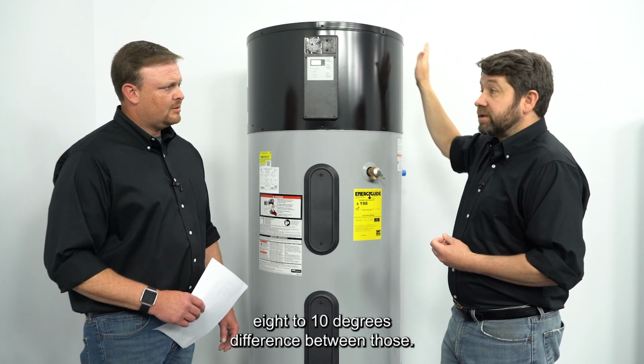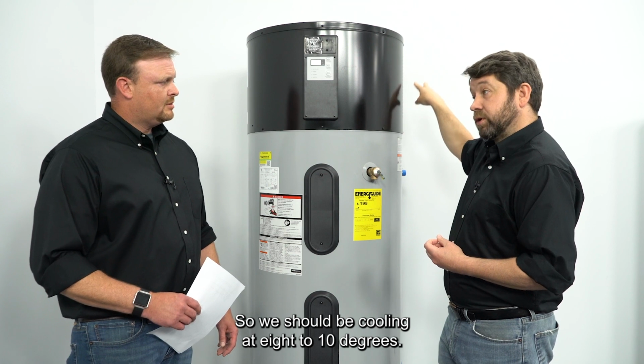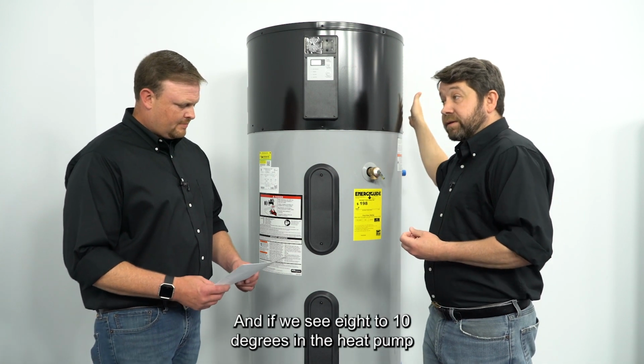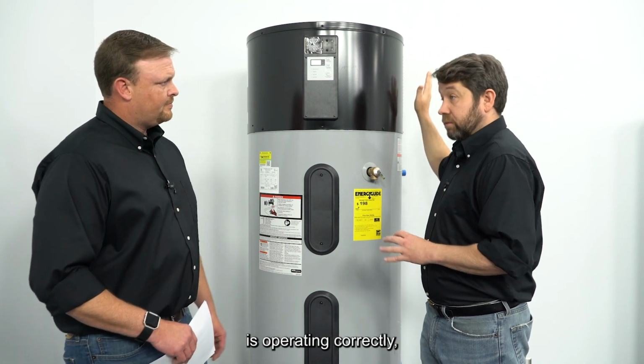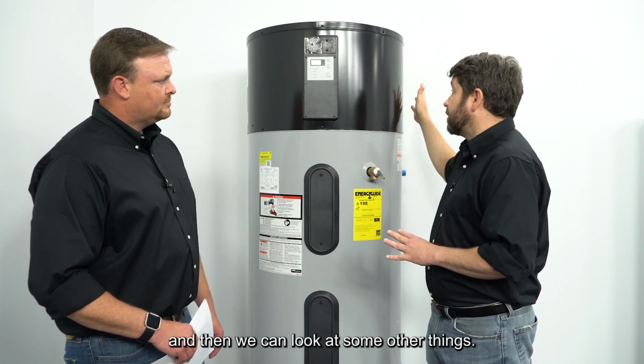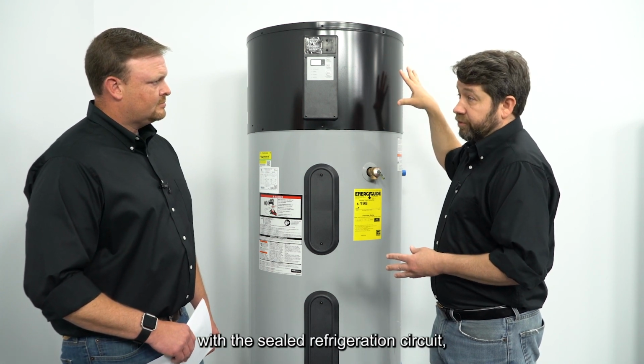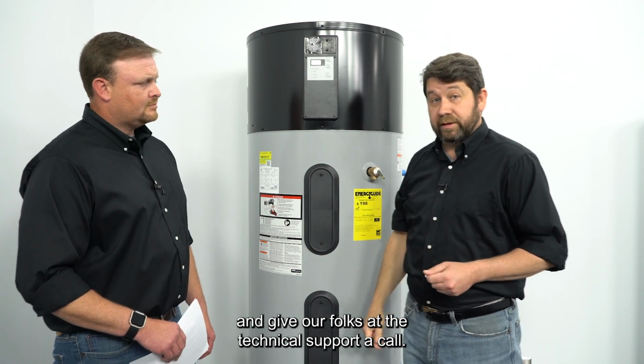Okay. And we should see 8 to 10 degrees difference between those. So we should be cooling at 8 to 10 degrees. And if we see 8 to 10 degrees, then the heat pump is operating correctly. Right. And then we can look at some other things. If we don't, then there's a problem with the sealed refrigeration circuit, and give our folks at the technical support a call.